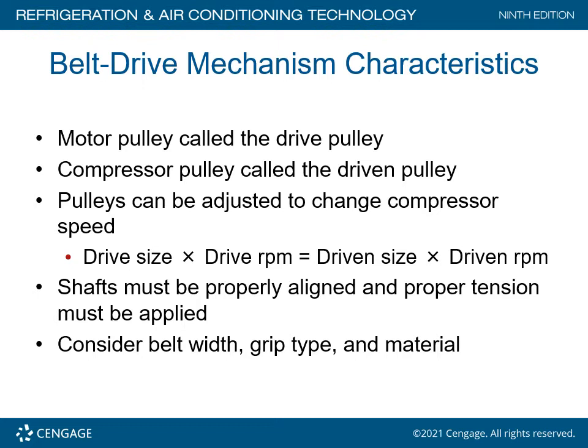Alignment is critical — the motor and compressor shafts must be perfectly parallel to each other. If they are not, you are going to have problems with the shaft seal. Simple as that.